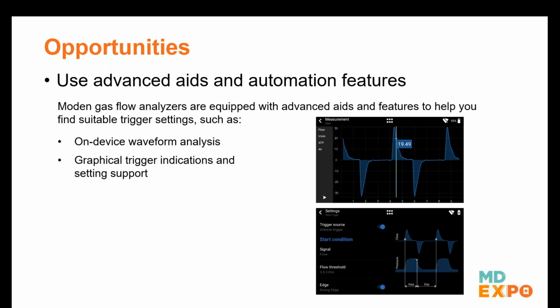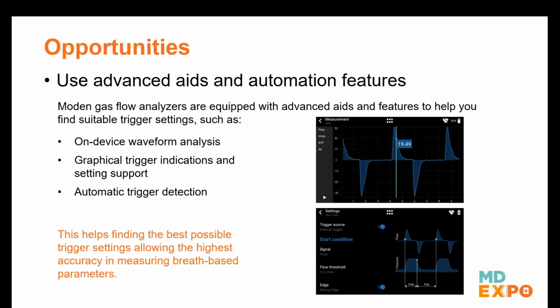And there are also features like graphical trigger indications, for example, as you can see in these pictures, that give you guidance. Okay, what are the impacts of my settings on my waveforms? Where am I triggering, on which waveform, and on what slope of the signal? And the latest gas flow analyzer generation even features automatic trigger detection. So these devices are able to analyze the flow and pressure waveform in real time and then find suitable trigger settings for you automatically. So just imagine how helpful that is in a situation we discussed earlier, when you have trigger levels that are dependent on the setting of your ventilator. With such an analyzer, it's just doing that automatically for you. All right, so this helps to find the most accurate trigger settings for the most accurate breath-based parameter measurements.